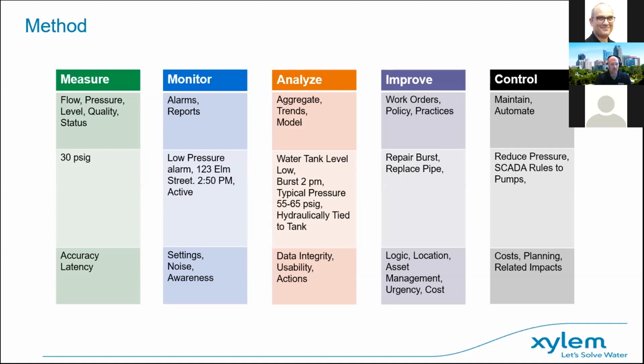Then you begin to take action — work orders, policies, and actions to repair the burst and replace that pipe. Eventually you might get enough intelligence to control the situation, using something like a SCADA rule to manage the pump against the pressure, reducing pressure in the lines to take that risk out, manage the system better, reduce leakage, and bring the whole control loop to closure. But it certainly starts with measuring and monitoring, getting enough intelligence to improve and know where to write those control rules. There's progression to be made along each step of the way, and that's what we want to talk about next.